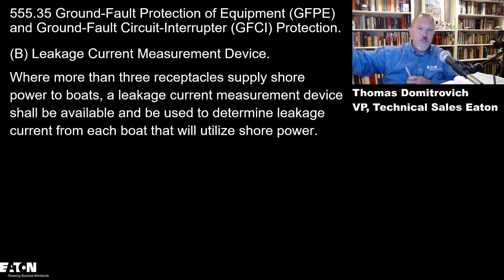100 milliamps on the feeders, 30 milliamps going to the boats, 4 to 6 milliamp GFCI on anything else. And don't forget about 210.8(B) for other than dwelling units, or 210.8(A) for dwelling units, if your boat dock happens to be in the backyard of a residential home.